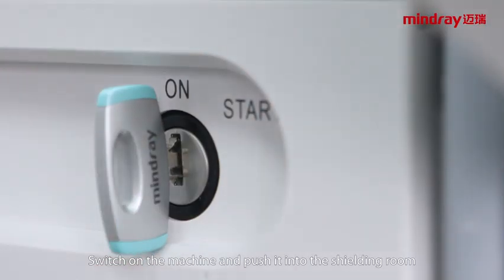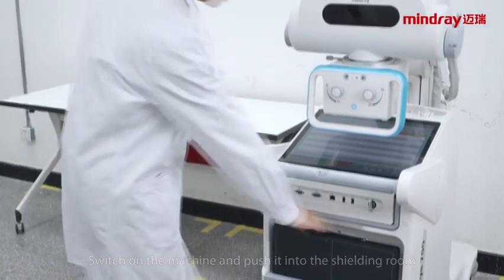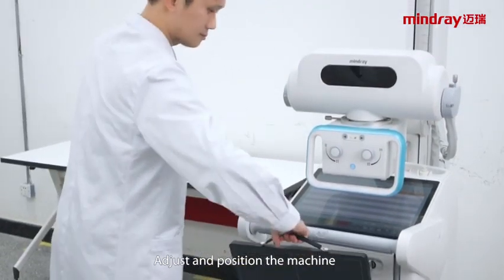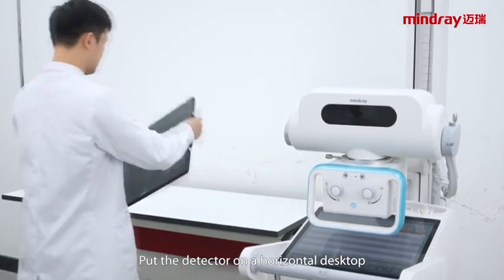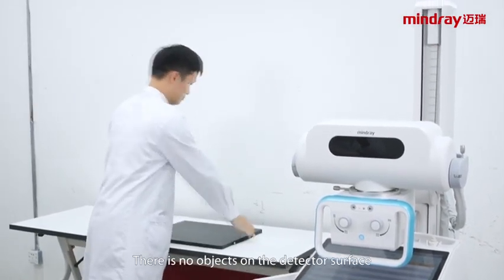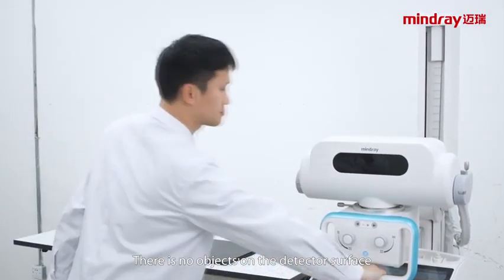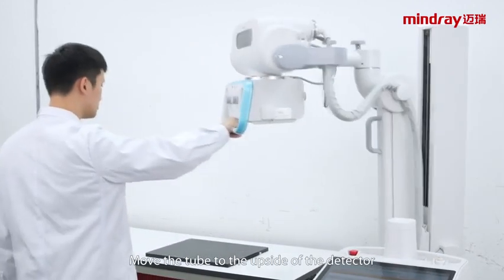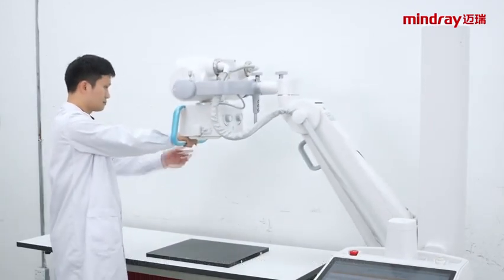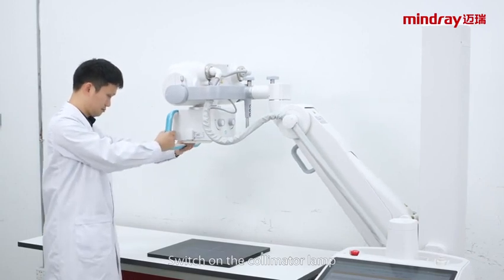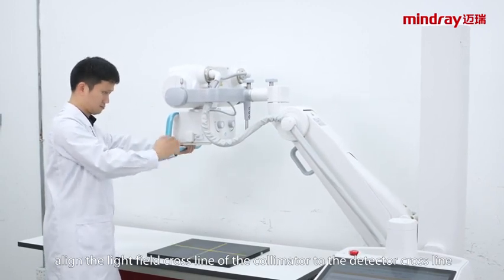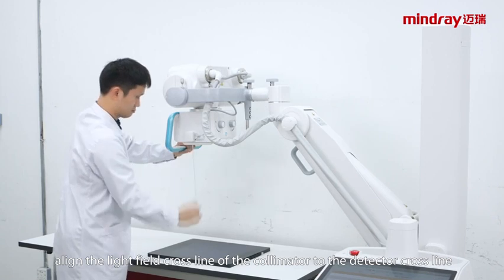Switch on the machine and push it into the shielding room. Adjust the position of the machine. Put the detector on a horizontal desktop. There are no objects on the detector's surface. Move the tube to the upside of the detector. Switch on the collimator lamp. Align the cross line of the collimator light field to the detector crossline.